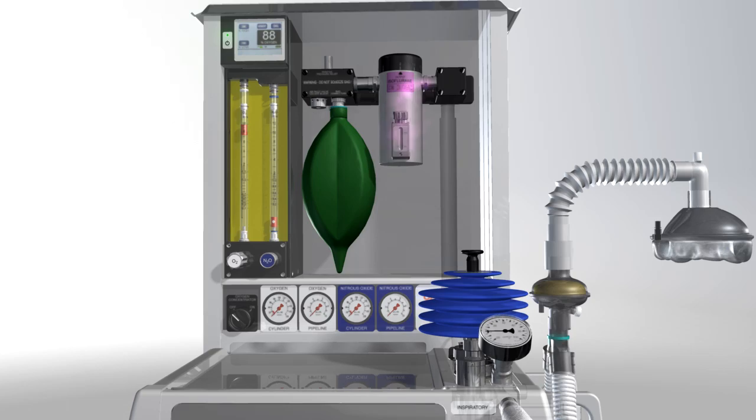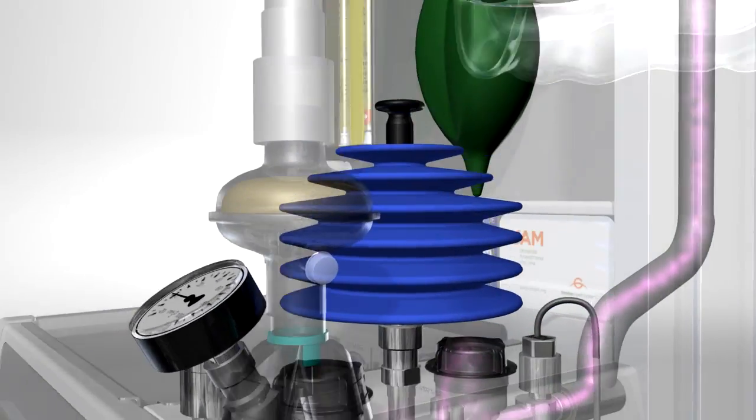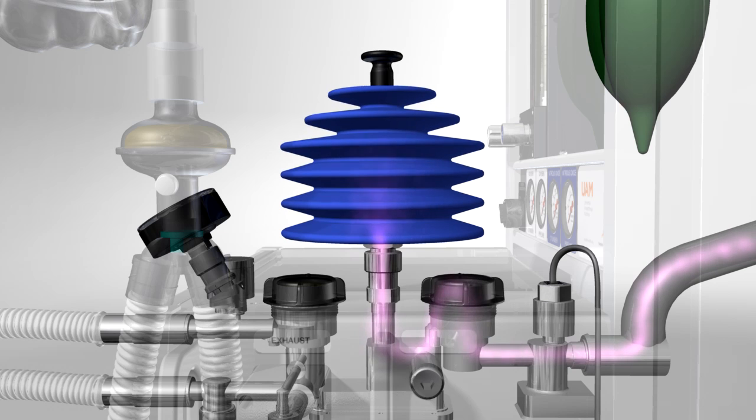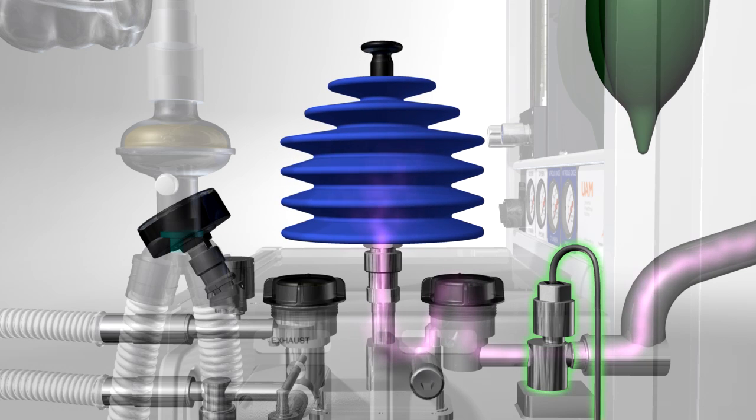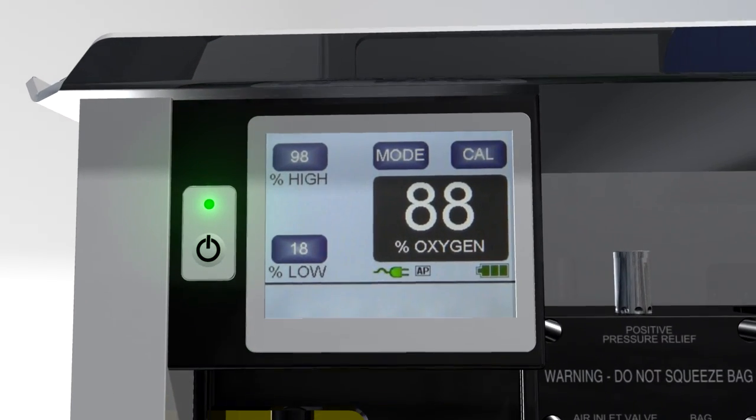The anesthetic gas flows from the back bar at low pressure to the breathing block and the bellows. A sensor reads the oxygen concentration of the gas passing to the patient. The reading is displayed on the oxygen monitor screen.